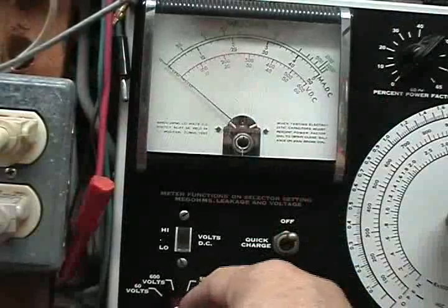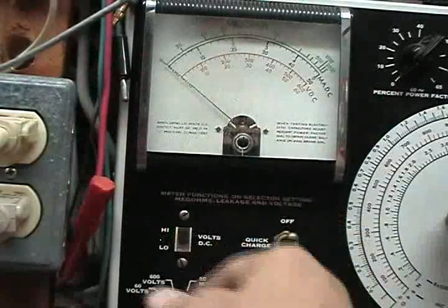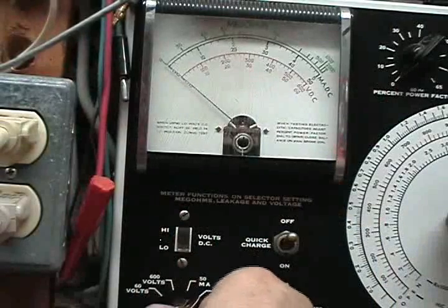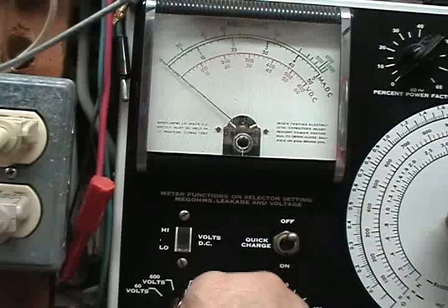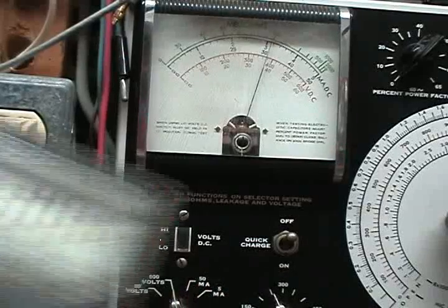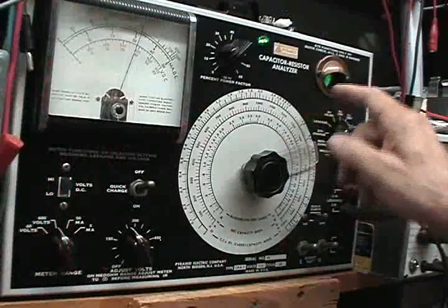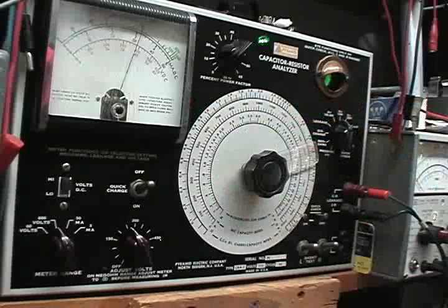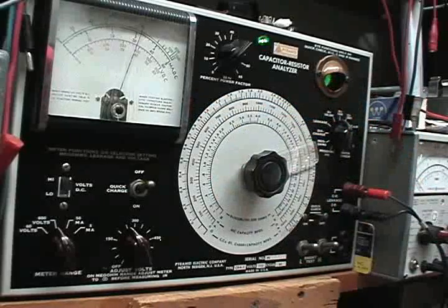As a matter of fact, the voltage went up to 419 volts when I went into these scales here, so the tester is not putting out precisely what it should be. Still putting out the 400 volts when we drop it back down to the voltage readings here.